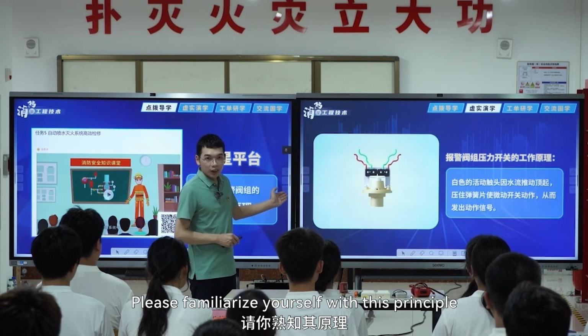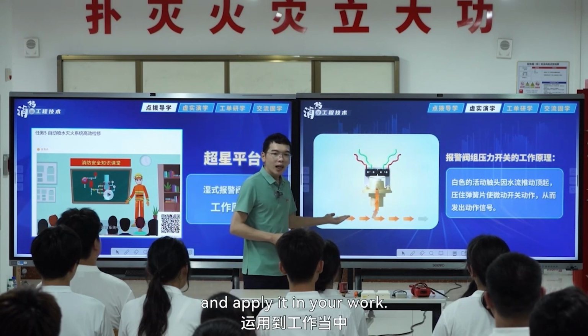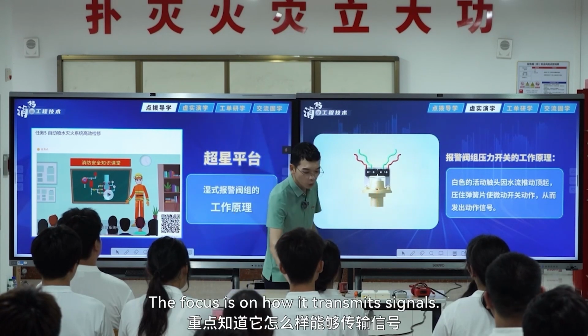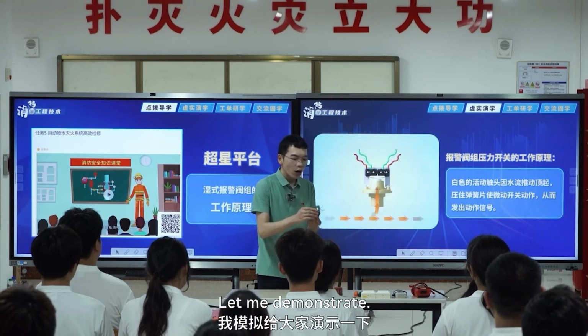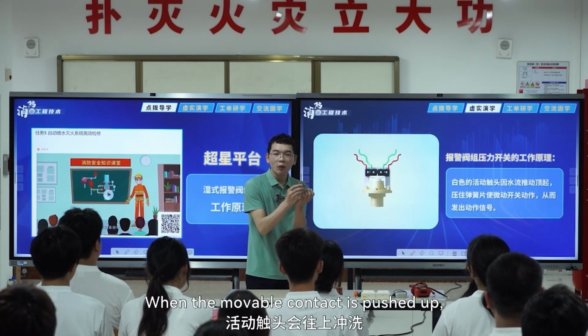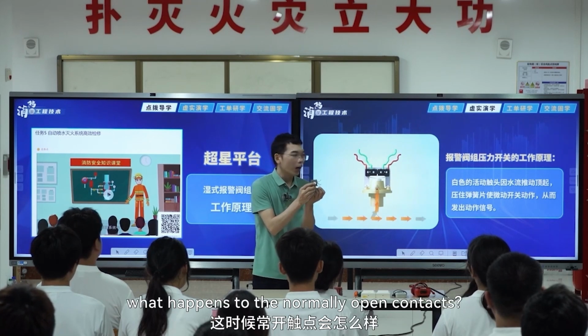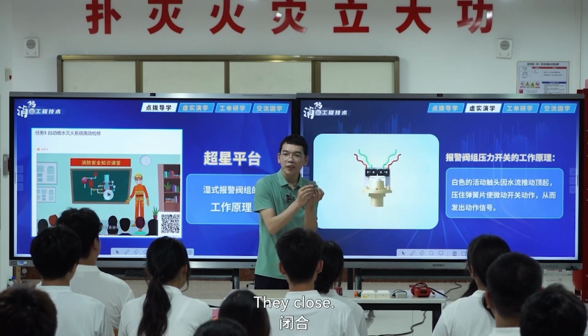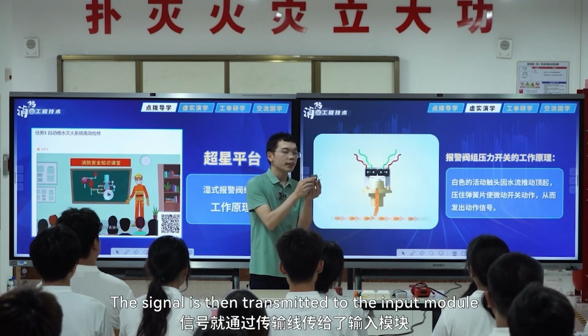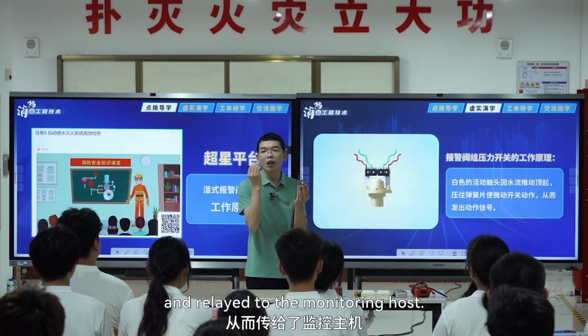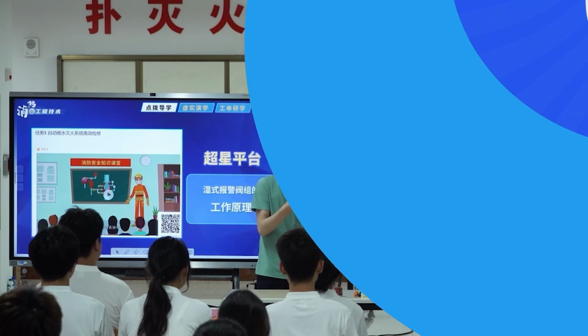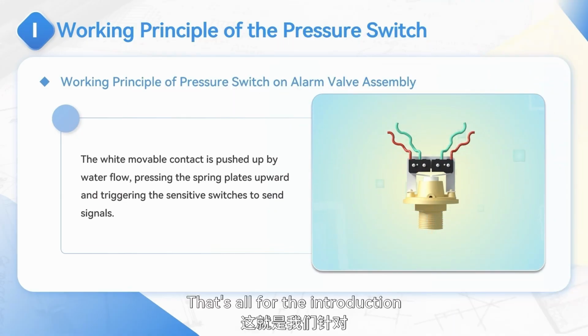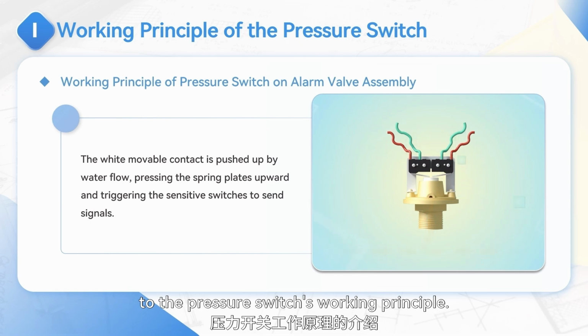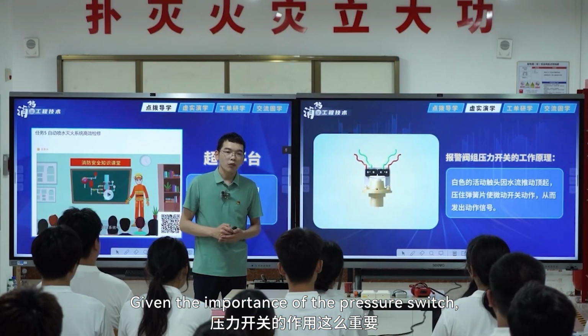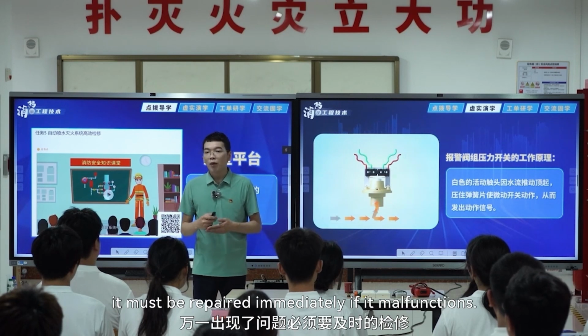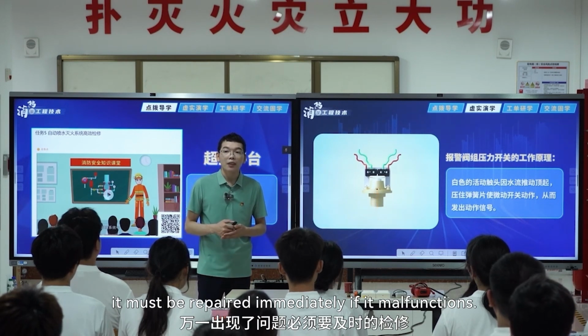Please familiarize yourself with this principle and apply it in your work. The focus is on how it transmits signals. Let me demonstrate. When the movable contact is pushed up, what happens to the normally open contacts? They close. The signal is then transmitted to the input module and relayed to the monitoring host. That's all for the introduction to the pressure switch's working principle. Given the importance of the pressure switch, it must be repaired immediately if it malfunctions.